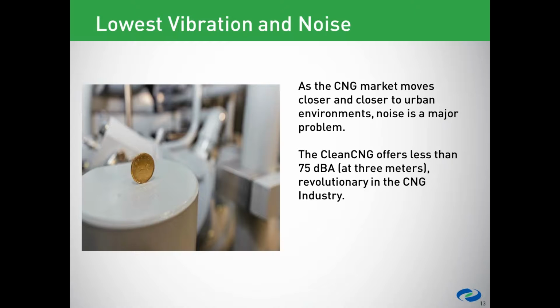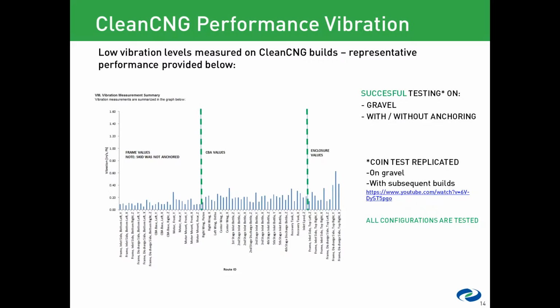This slide shows a number of test results on a 250 horsepower 5-stage compressor built and tested here at the factory. A number of different areas were tested for vibration levels. As you can see, the maximum vibration level achieved in any location on the package was below 0.8 inches per second peak-to-peak vibration velocity. Typically, the cutoff for vibration is 1.2 inches per second, and in all cases we're much, much lower than that cutoff.